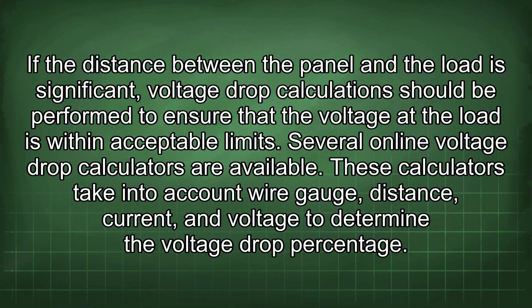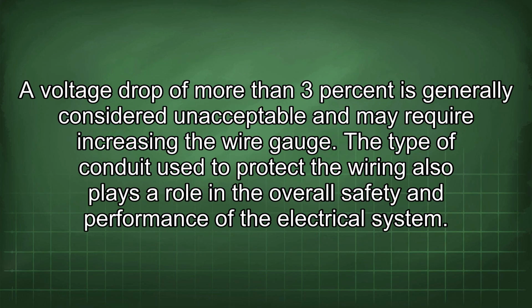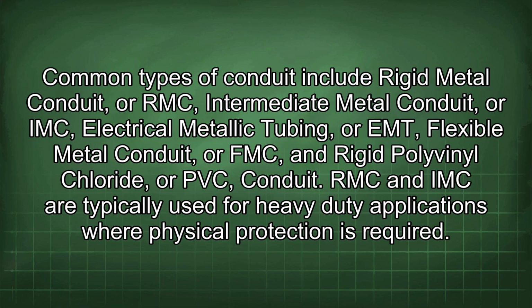Several online voltage drop calculators are available. These calculators take into account wire gauge, distance, current, and voltage to determine the voltage drop percentage. A voltage drop of more than 3% is generally considered unacceptable and may require increasing the wire gauge. The type of conduit used to protect the wiring also plays a role in the overall safety and performance of the electrical system. Common types of conduit include rigid metal conduit, or RMC, intermediate metal conduit, or IMC, electrical metallic tubing, or EMT, flexible metal conduit, or FMC, and rigid polyvinyl chloride, or PVC conduit.